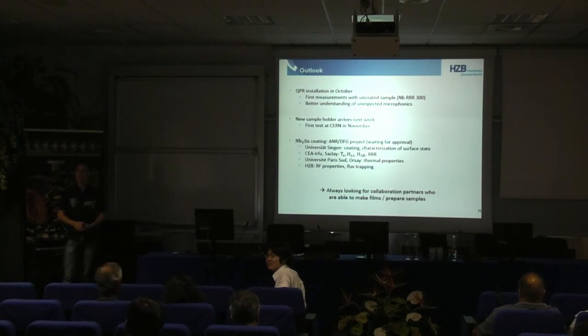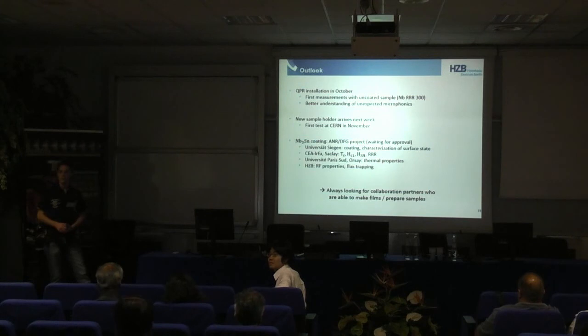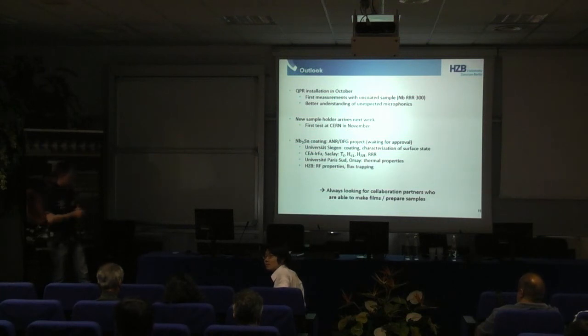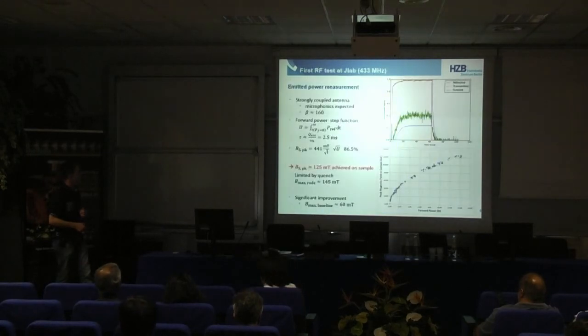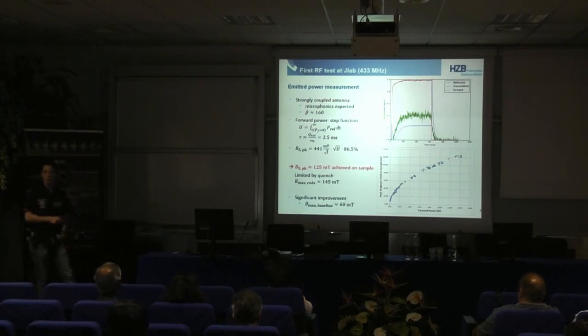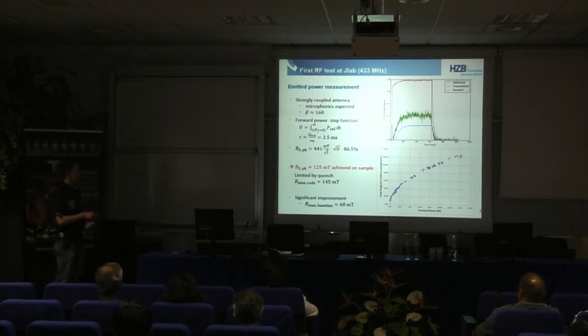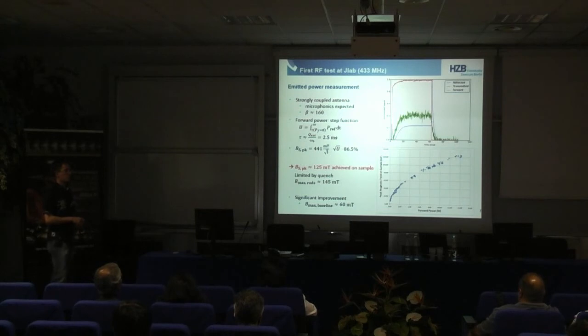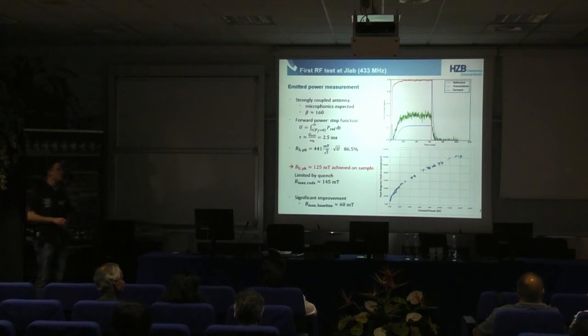A correction was noted: the valley is on the side of the sample in the CERN version, not on top of it. The question about the quench field: it was measured in pulsed mode — the time scale is 60 milliseconds — and this measurement was done at 1.8 Kelvin.